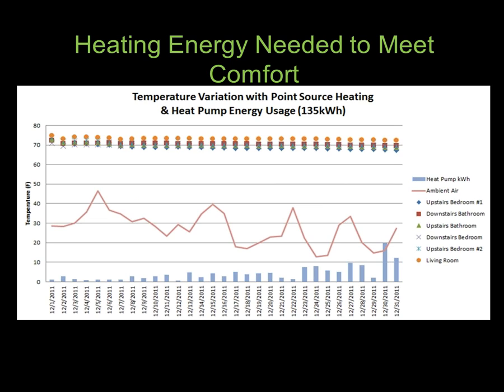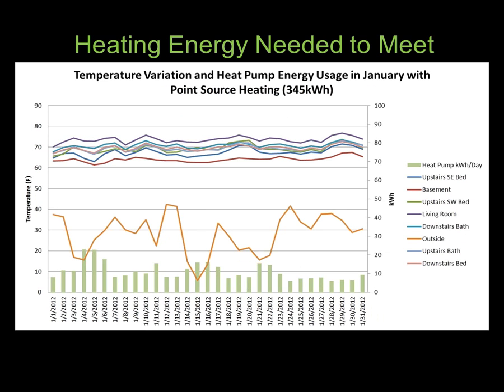And when we start to get further into the heating season, here we are in December. This shows the entire month, and the total energy usage for that heat pump to keep the building more or less between 68 and 72 degrees was 135 kilowatt hours. If you were to take this and say, what's that equivalent energy to? Well, that's a couple hundred watt light bulbs running continuous. So that is the impact of this high performance envelope on the total heat demand needed to keep the building at a comfortable temperature in northern Vermont.